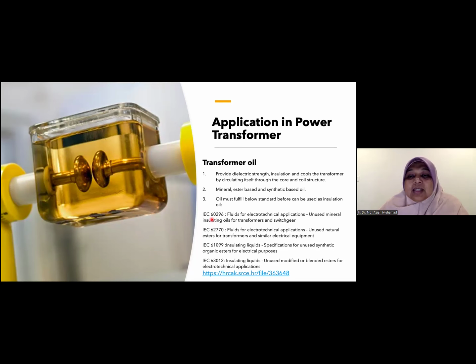There are different standards for different base materials. IEC 60296 is for mineral oil. IEC 62770 is for ester oil, which is new oil.